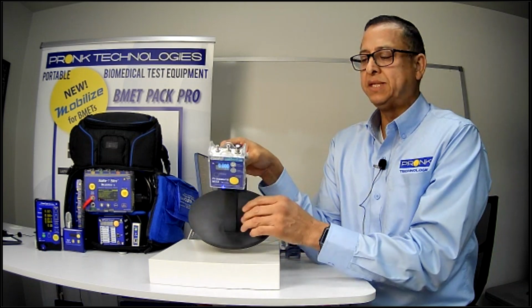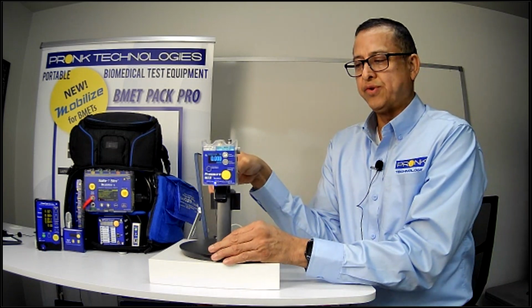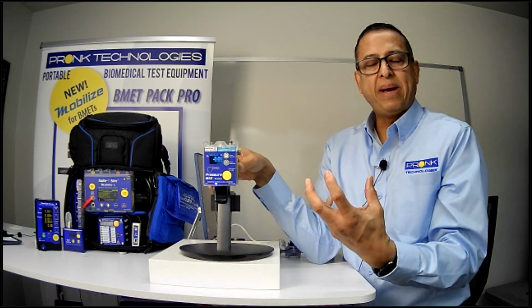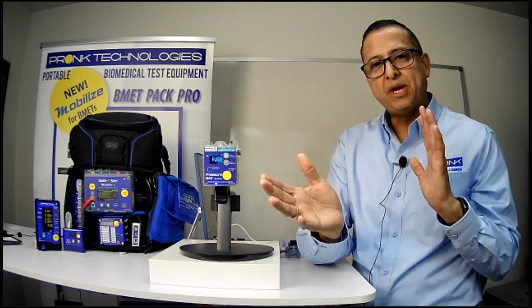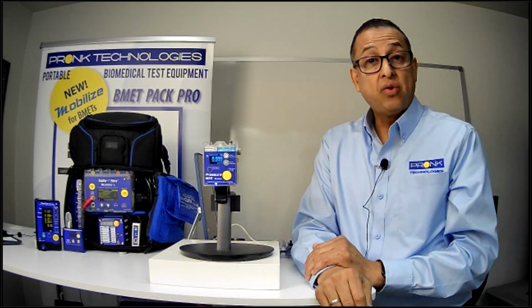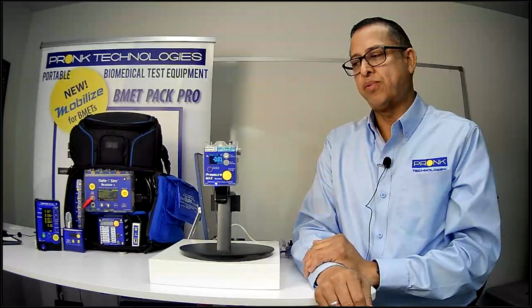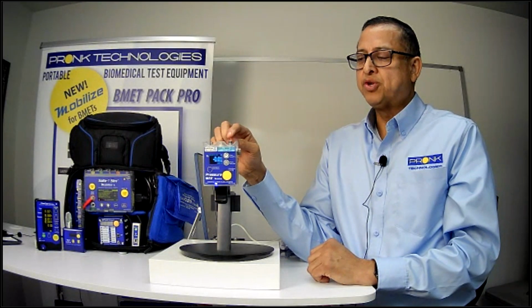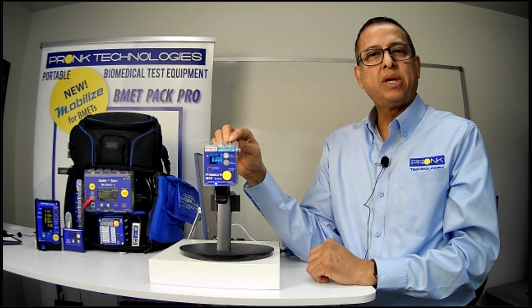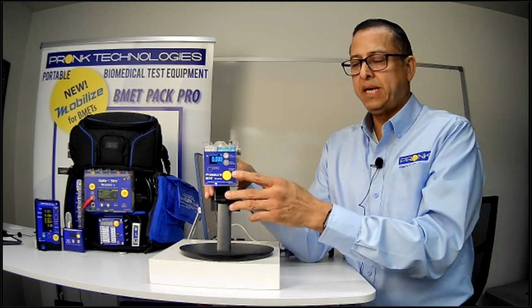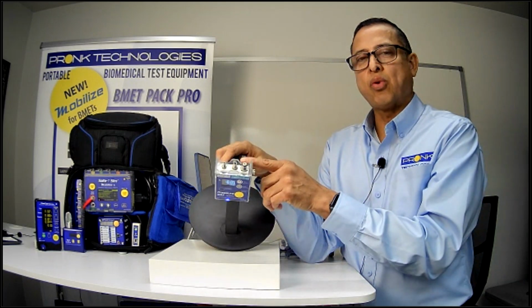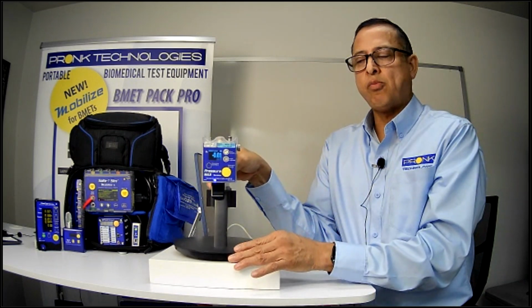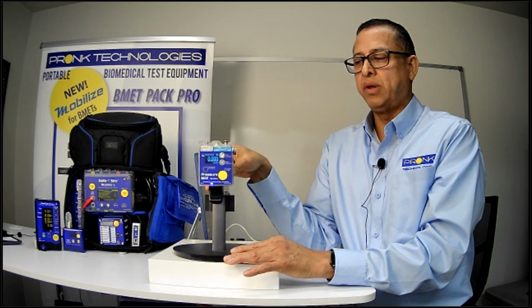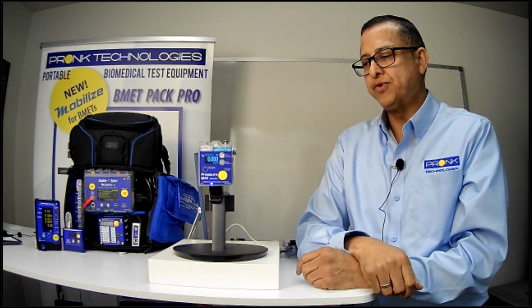The unit also has the ability to do differential pressures. And so that can be beneficial if you're testing devices that you need to measure differential pressures with. It measures differential pressures between the high port and the differential port, which you'll see here in the center, or also between the low port and the differential port.